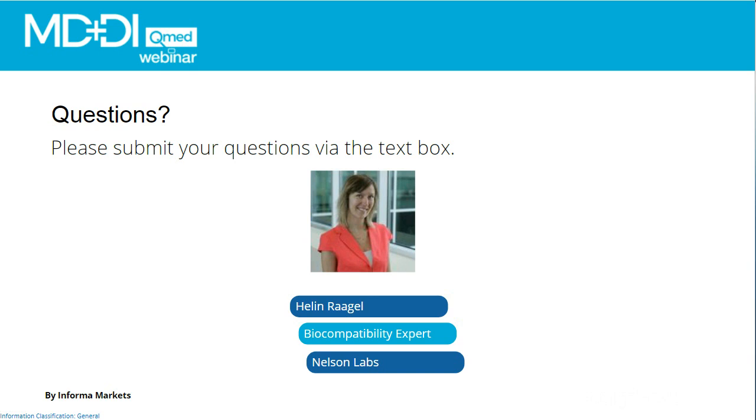And then you need to have a toxicologist look at the tolerable exposure versus what is coming out of your device to determine whether there is a potential impact or toxicological concern to the patient. So that's really what we want to do: we want to have what is coming out. If you have data showing that this amount is already shown to have an IC50 that will make a concerning result in a cytotoxicity test, then prove with available data that from the toxicological perspective, this is not going to be a concern for the patient.